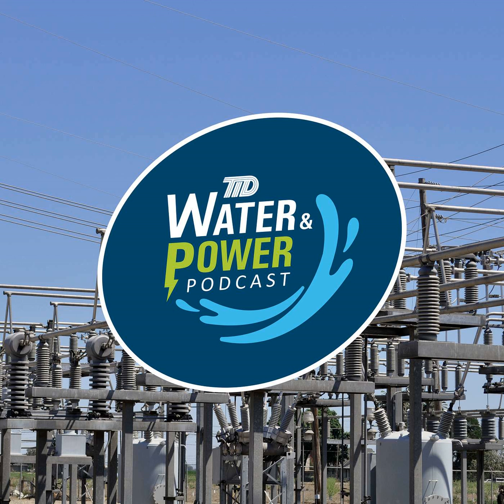By having that shared vault, it actually caused more heat to be generated from neighboring conductors. So in order to operate safely and make sure we didn't damage those conductors, we had to derate or reduce the amount of capacity each of those lines could serve. So we were in a situation where you could add more capacity for the transformer, but you couldn't get the capacity out on the distribution system.